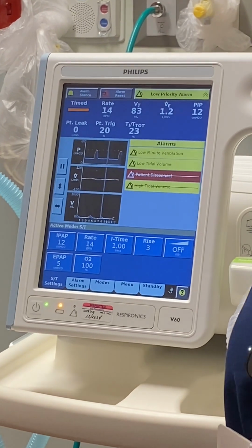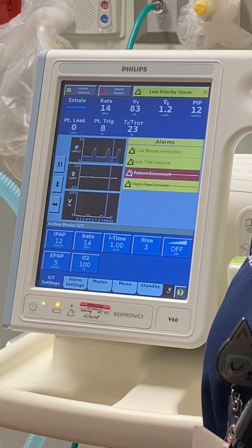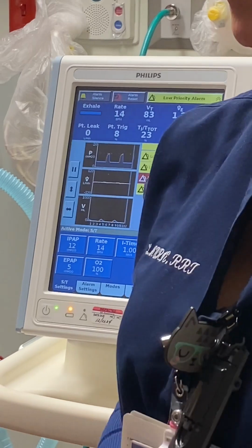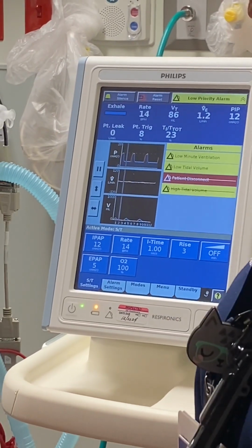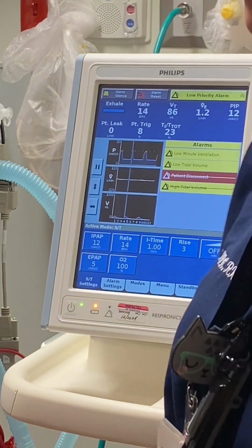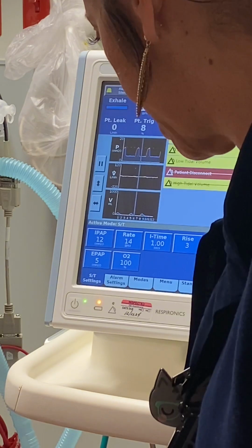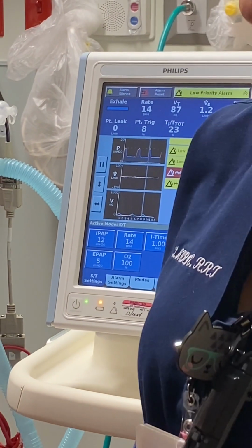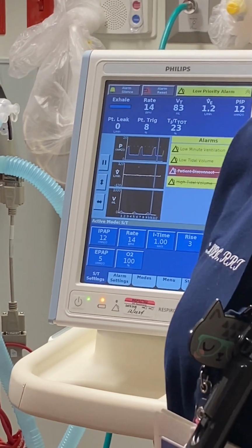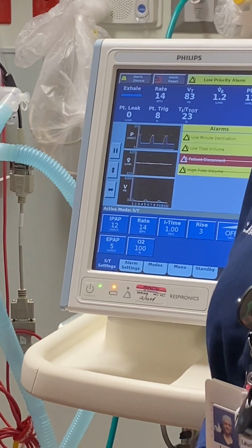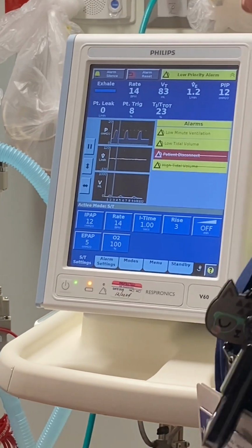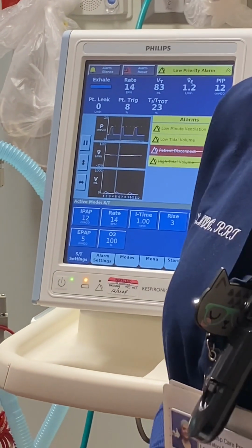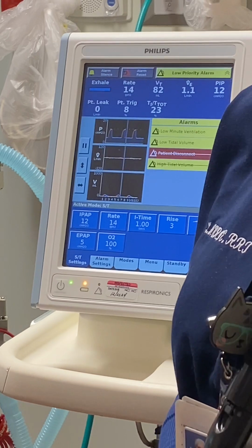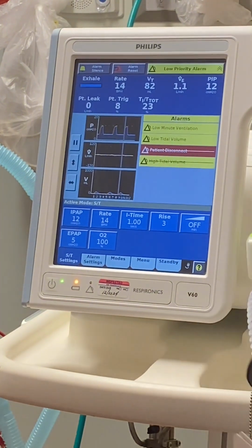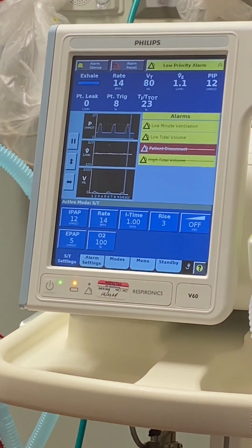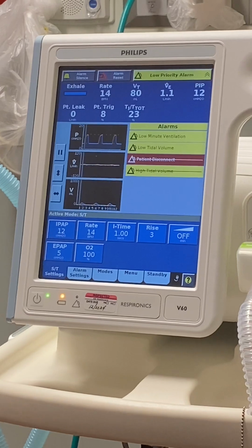I time is how long it keeps up that pressure. The inspiratory time. So when it administers that pressure, it keeps it up for 1 second. And it says that on there, 1 second. So that helps oxygenate too. Rise time is how fast it's delivered, the pressure. How quick it is in milliseconds. That's something respiratory could do also. But when you're charting, you're going to mainly chart the IPAP, the EPAP, and the backup rate and the FiO2.